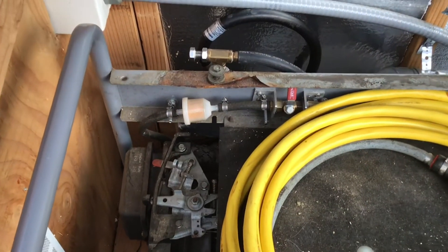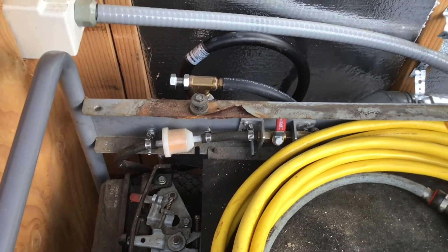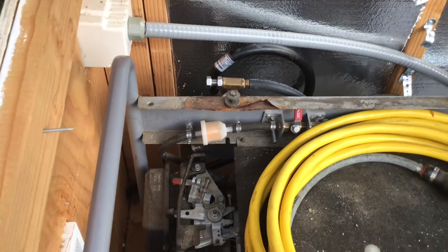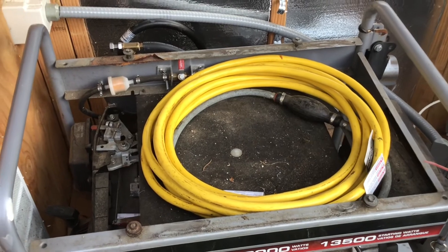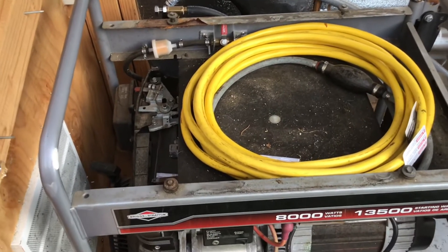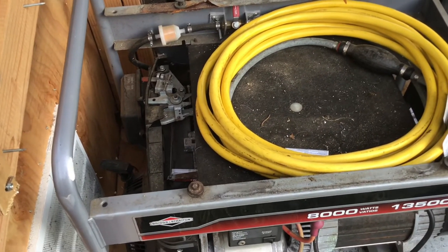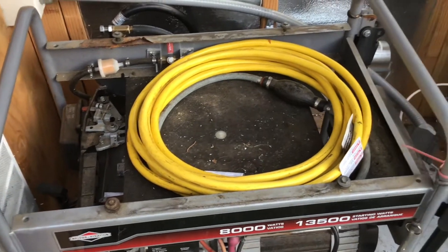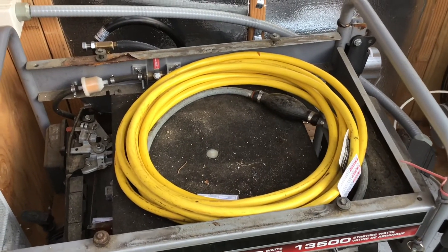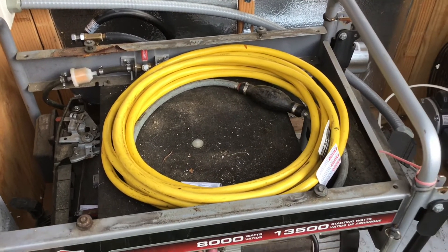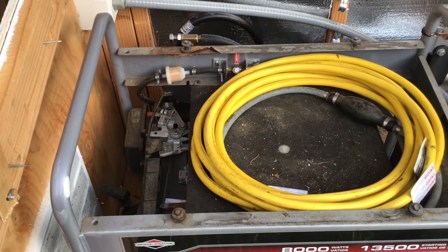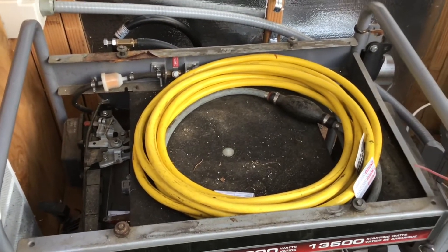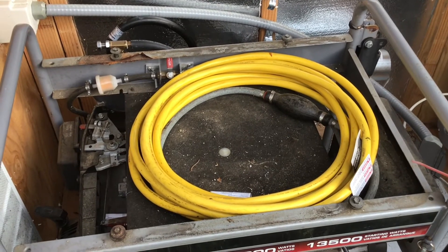Two other things. One, you'll notice the fuel filter and the valve right there. I did plumb this to run off of gasoline. It's actually set up to hook into my boat tank. So if I do need to run off gasoline, if the natural gas goes out, we run out of propane, I can hook up to that. And then the big yellow thing is the power cord. That's a 30 amp 240 volt cord. We plug it into the outside of the shed here and plug it into the house. And that sends power into our transfer panel.